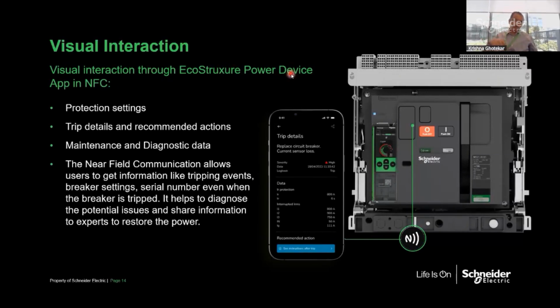So the sign of the power will be negative. To make it reverse, you can change the power sign. Multiple other things you can do via EPC, EcoStruxure Power Commission. On top of that, let's say, for example, you have a wireless trip unit of MTZ Active connected to the PAS gateway, and you want to do communication testing with ACB, MTZ Active, with NSX breaker, with Acti9 MCBs, with the power meter and so on.